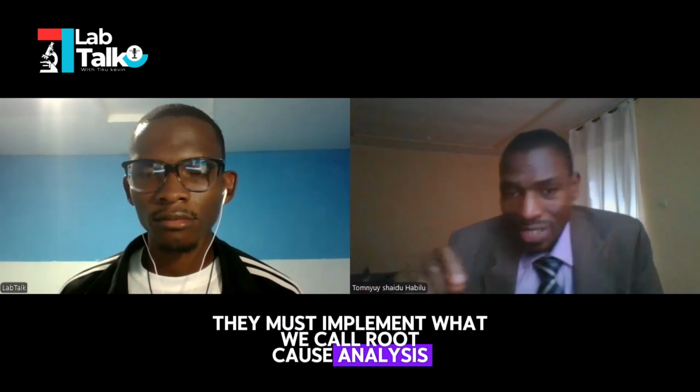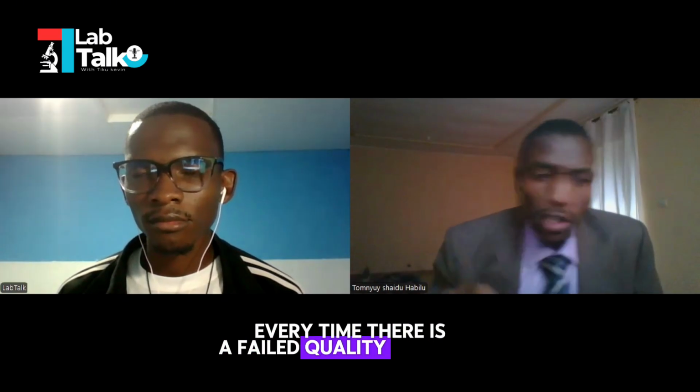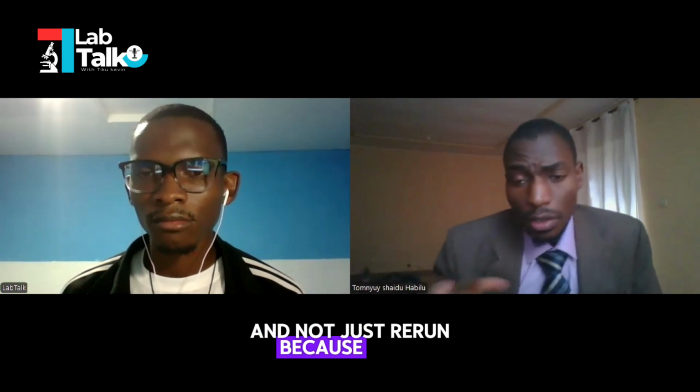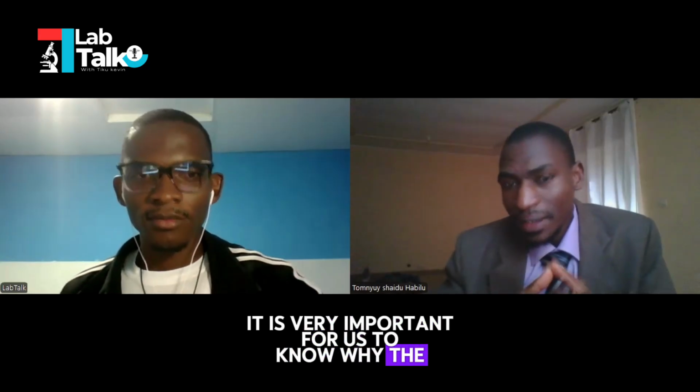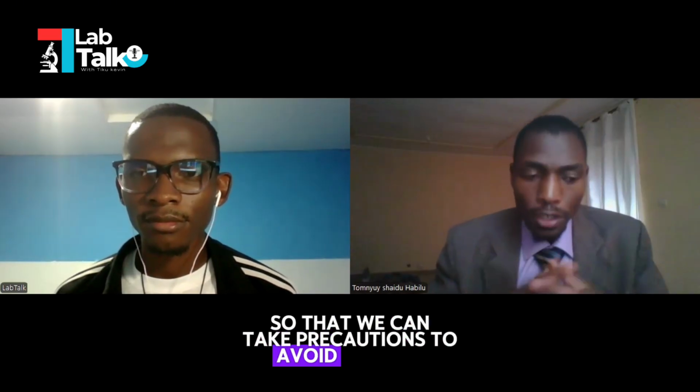Now, for systemic errors, for labs to improve, they must implement what we call root cause analysis every time there is a failed quality control, and not just rerun, maybe because they want to rush home. When the quality control fails, they simply just rerun or swap. It is very important for us to know why it failed, so that we can take precautions to avoid future cases. And then another aspect is regular training of staff on ISO 15189.